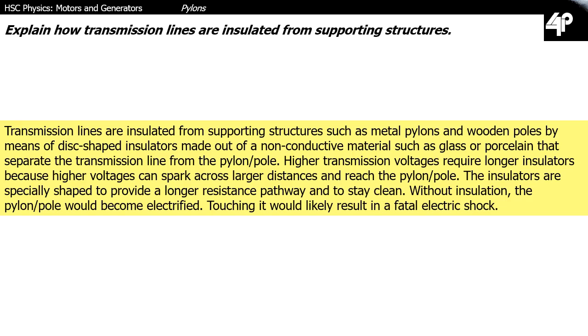Transmission lines are insulated from supporting structures such as metal pylons and wooden poles by means of disc-shaped insulators made out of a non-conductive material such as glass or porcelain, separating the transmission line from the pylon or pole. Higher transmission voltages require longer insulators because high voltages can spark across larger distances and reach the pylon or pole. The insulators are specially shaped to provide a longer resistance pathway and to stay clean. Without insulation, the pylon or pole would become electrified, and touching it would likely result in fatal electric shock. That's really all you need to take away from this one.